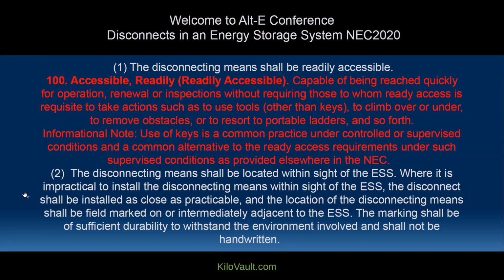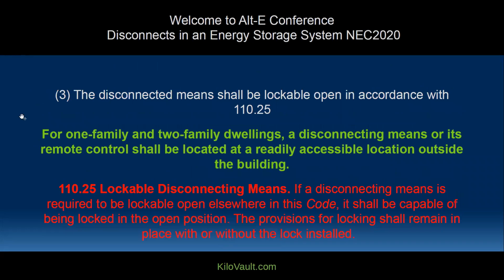Also, nowadays we're requiring field markers for your ESS. Disconnect means shall be lockable in accordance with 110.25, open and basically held in the open position, so that we have no potential at this point while servicing. There's no chance of someone getting electrocuted.